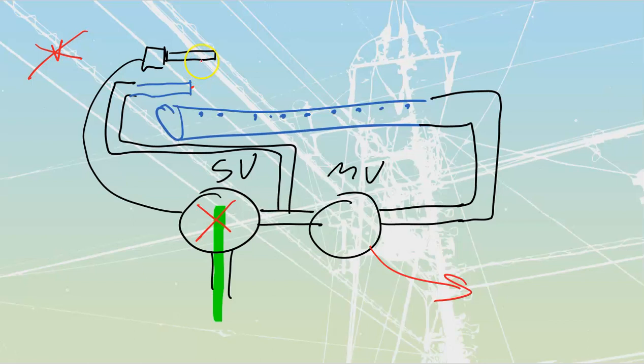You also want to go and adjust your thermocouple. Thermocouples are usually mounted onto thin pieces of metal so that they don't carry a lot of heat to other places, right? It's going to be a large metallic piece over here, and if this thing is bathed in heat, it would carry back to other stuff. What happens over time is that these things can warp. There's a lot of heating and cooling cycles, so they warp, and sometimes they push out of the area of the flame, so you sometimes have to put them back in. Or it could be that the orifice is starting to ash over, and so it's changing the shape of the flame. Just make sure it's fully bathed inside of the flame. In some cases you also have an additional shield that curls over the top so that the flame is forced over top of that. You can adjust that flame shield to once again make sure it's completely bathed inside of that pilot flame.